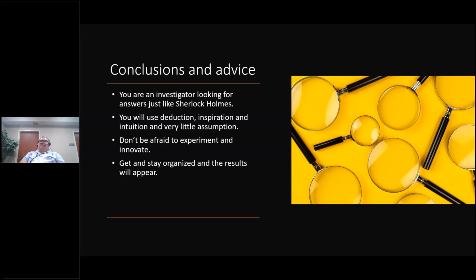You've got to verify. Don't be afraid to experiment and innovate. There's a mantra we had in commissioning: if it's not broke, break it. The engineers were kind of afraid of what that really meant, but it meant you're going to push it, push it to the limits to find out where you can operate, because if you don't know, you have to find out. There's got to be a way for you to know how far you can go and where you can't go past that point, and that's the only way to do it, if nobody can tell you, if you didn't have the information to begin with, like a tab report. Commissioning is supposed to push it to the limit. The tab report is supposed to give you the minimum and maximum operating points in the system. If you didn't have that, you're going to have to find out for yourself.